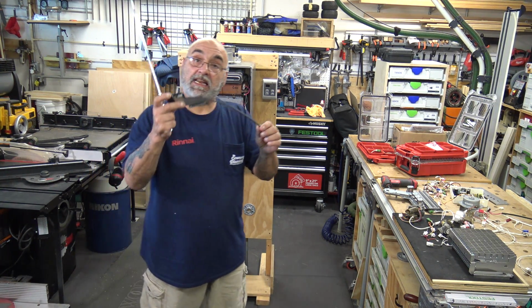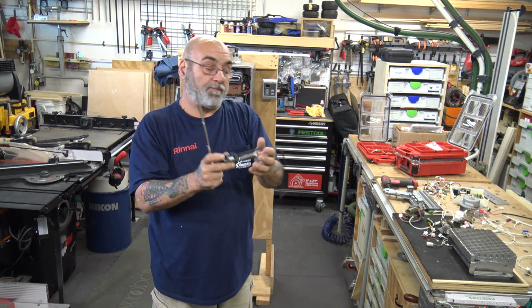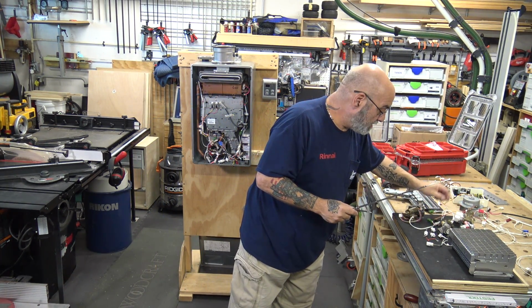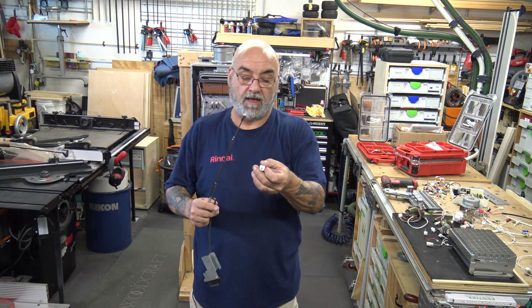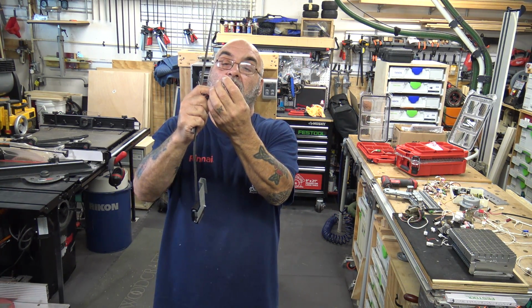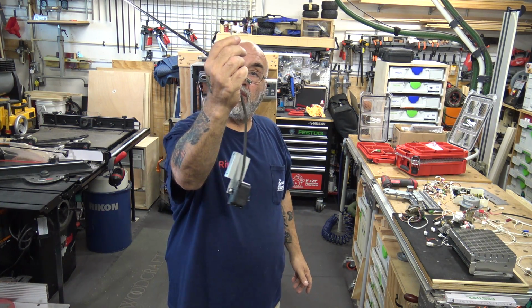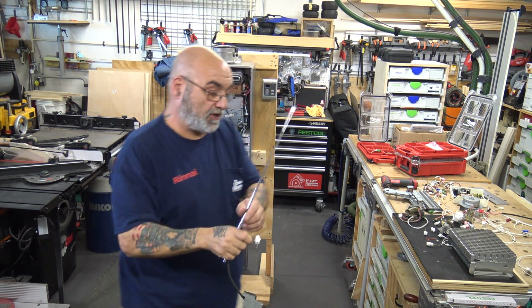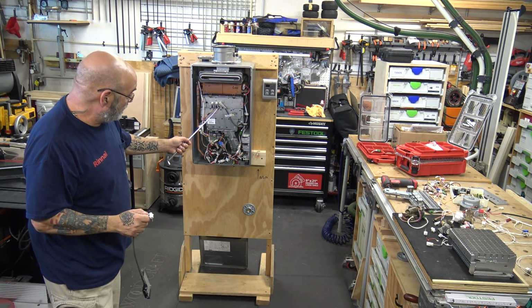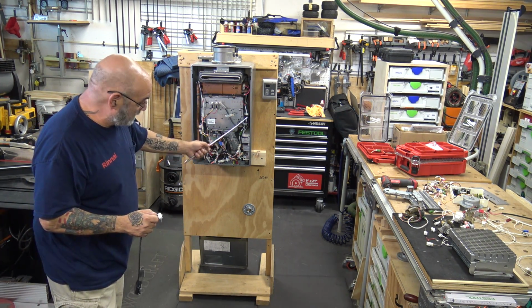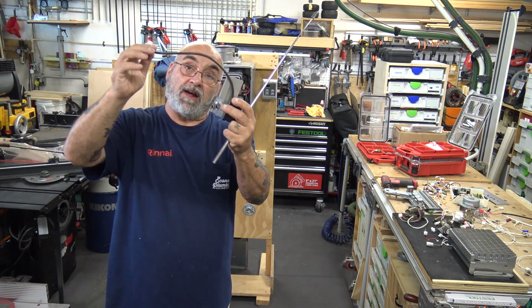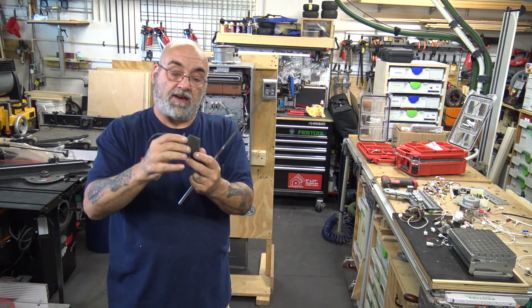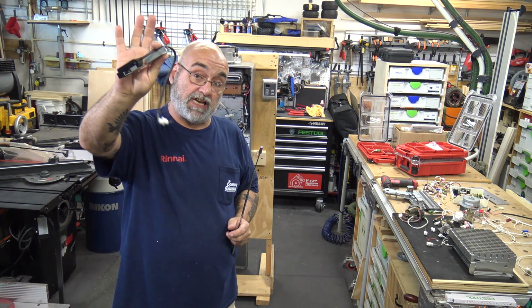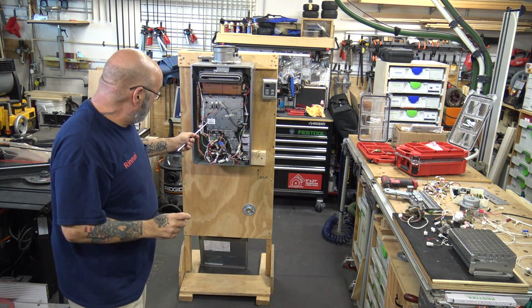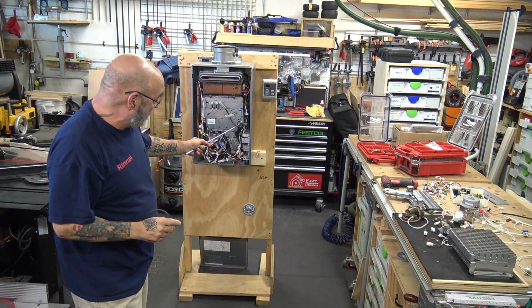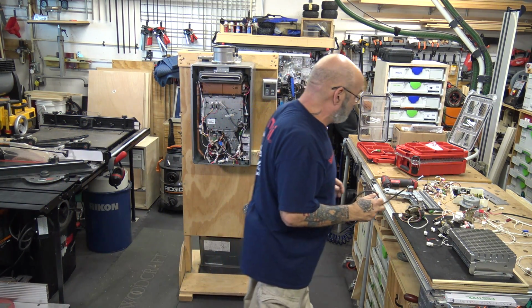We'll send a signal to the igniter, which would then ignite the burner. And that is the igniter with the ceramic piece, which is right here in that rubber boot. You see, you got the black wire that goes back to the igniter. Here's the black wire, goes to the igniter. Now, this is not part of the wire harness, as you can see. It's a separate piece.